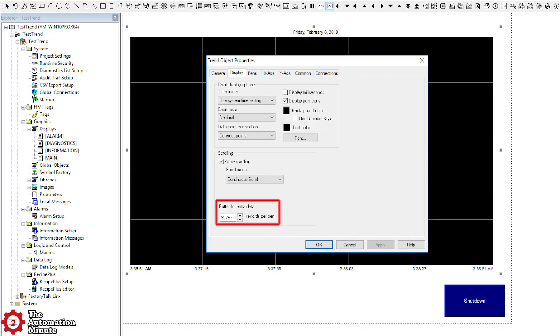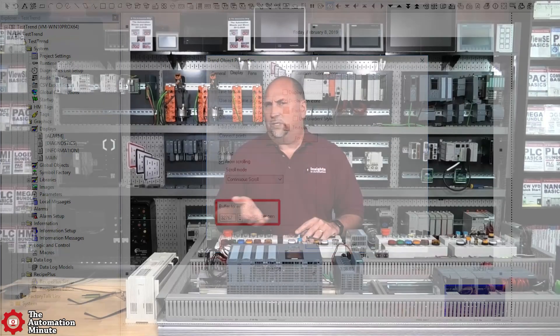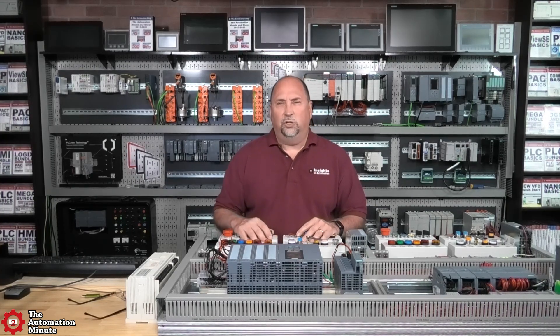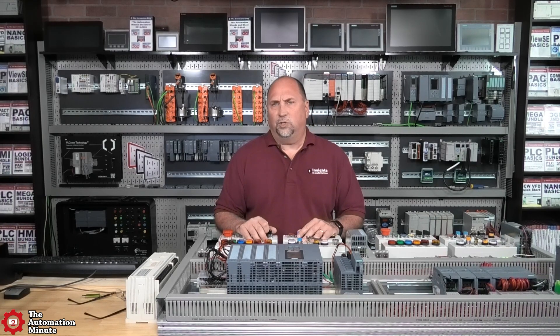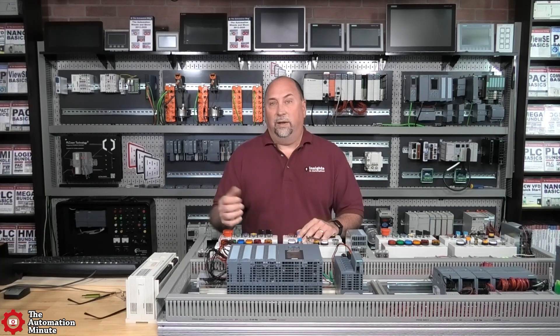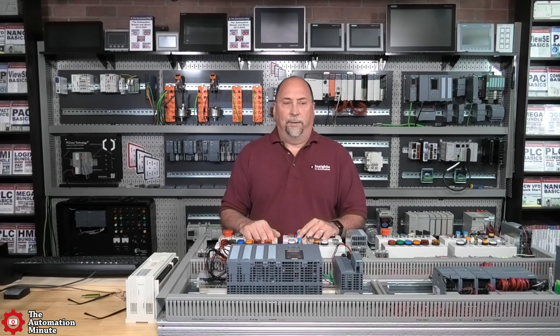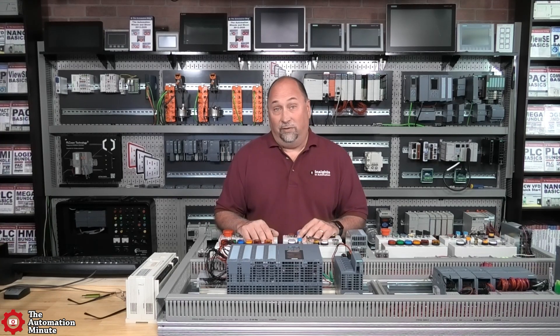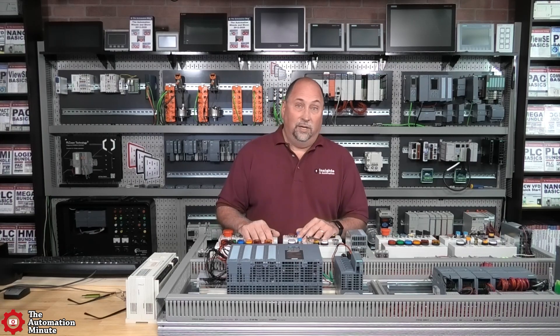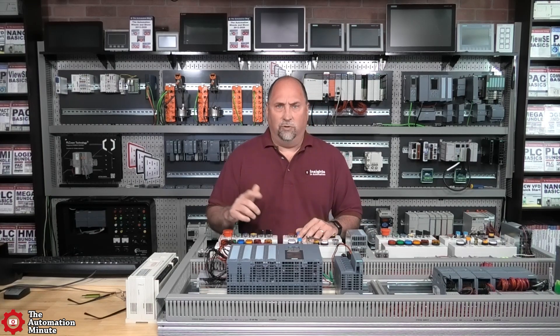It's a great way to demonstrate the difference between the onscreen buffer and the historical data. Of course, the onscreen buffer is much smaller than the historical data. You can set a screen to stay open on top, and there are tricks you can do — like always updating in the background to try to keep more of that onscreen buffer. But at some point, if you're logging every second, you're going to run out of memory, because this is an HMI, not a PC with a terabyte hard drive.